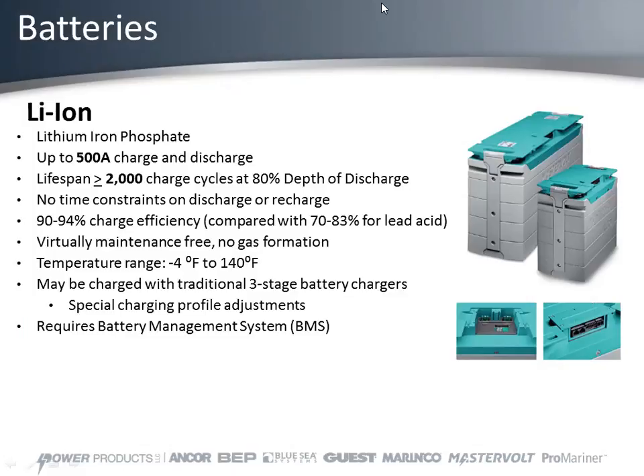It doesn't mean that if you have a 20 amp discharge you get 10 hours out of it, because that's not a linear curve - you're probably going to get 6 to 8 hours out of it. With lithium technology, it doesn't matter if you discharge it in an hour, 5 hours, 20 hours, or 100 hours. You always have that same capacity available.